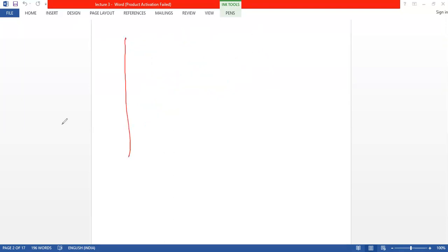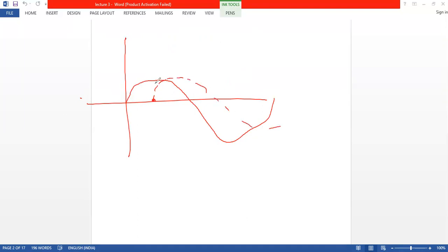So if this is the system voltage, the flux will start from here. When supply voltage is at peak, the flux requirement is 0. It can start from 0. But if you extend this to here, when supply voltage is at zero crossing, it requires negative flux, negative peak. This cannot happen. Okay.